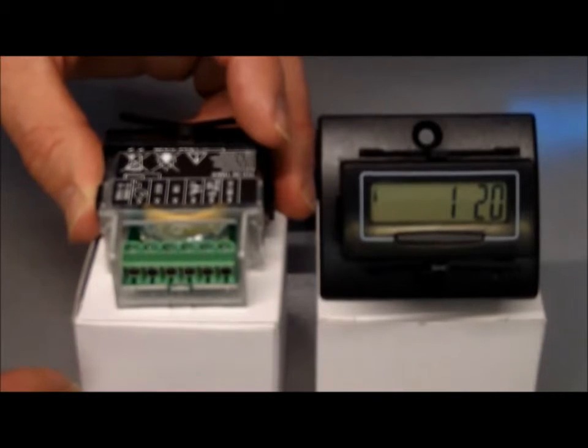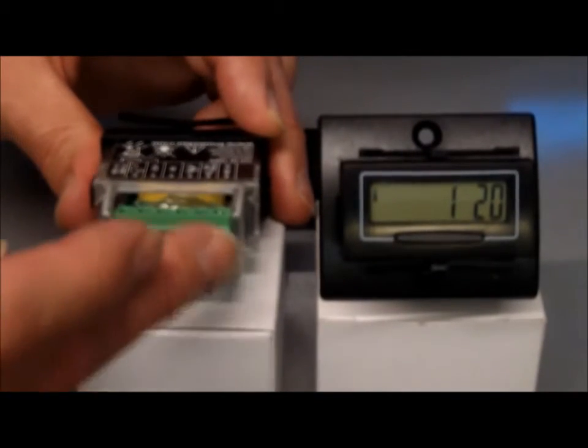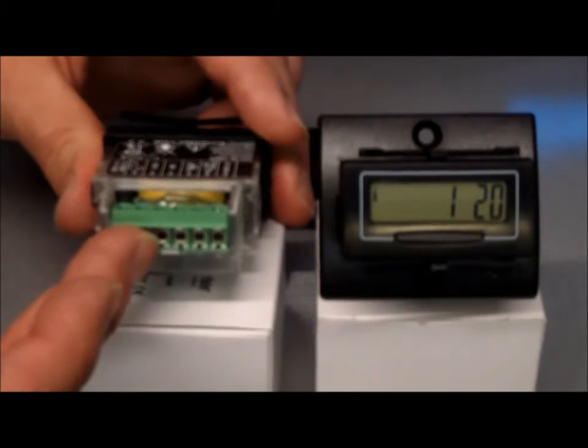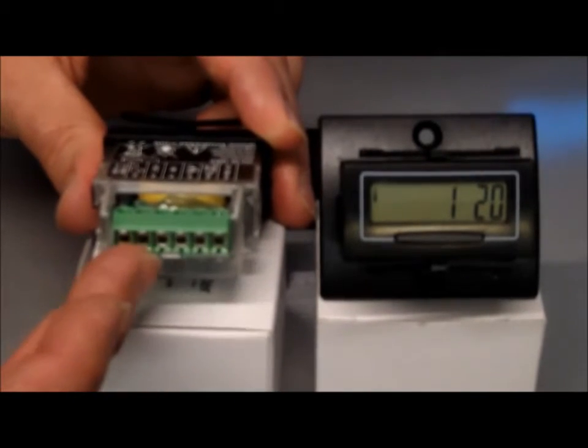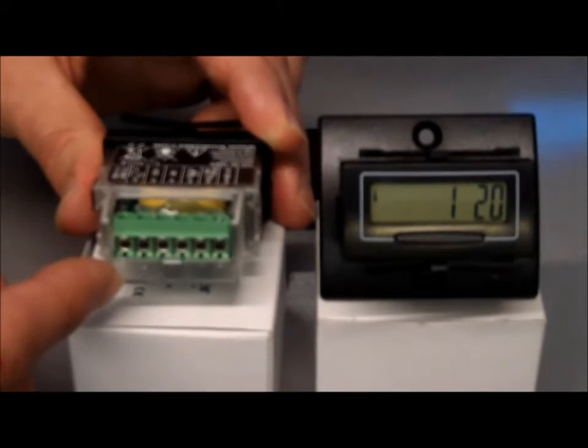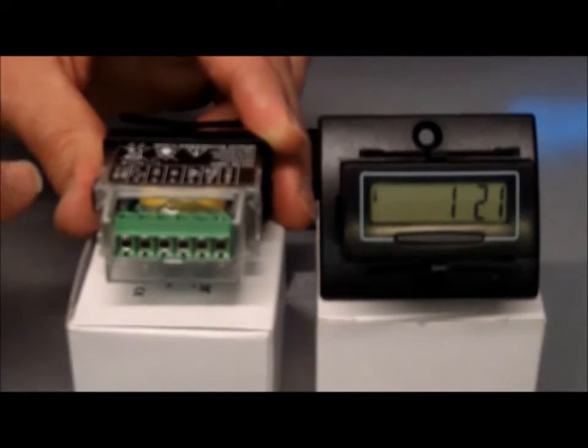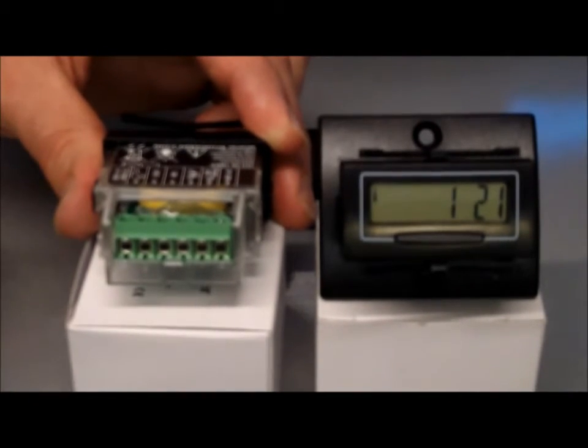The reset can be disabled using a link on the back screw terminals. That's the easy way for the wires to be connected, on this terminal block on the back. Different modes of timing - minutes and seconds, or seconds on its own - are all changed by jumper pins on the side of the unit.